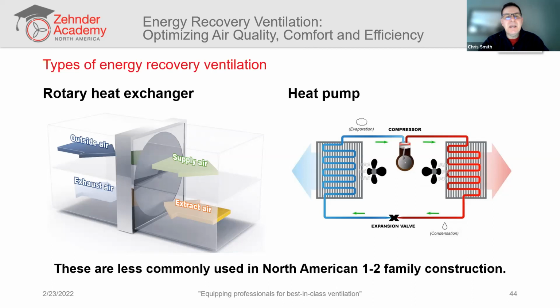And as the wheel spins, the wheel is made up of a coil of sort of corrugated material. And so as the wheel spins through whichever of those air streams is the warmer, depending on the season, it will collect the energy from that airstream. It will rotate around, and then as it goes into the other airstream or the other plenum, that airstream will collect the energy and deliver it. So if it's wintertime, it'll collect the energy from the indoor and then spin around and deliver it to the outdoor air. So as the outdoor air is delivered to the building, it is coming in warm.